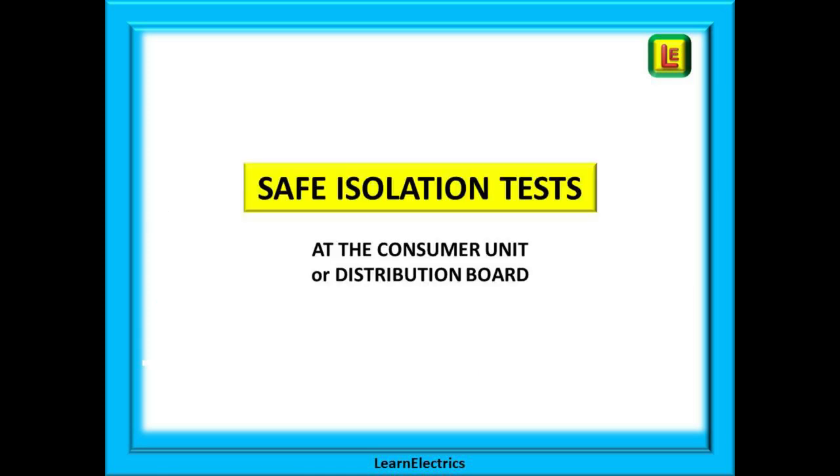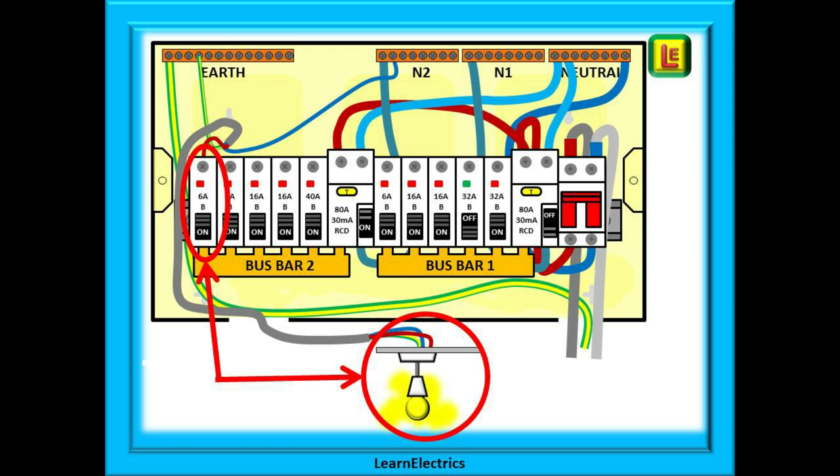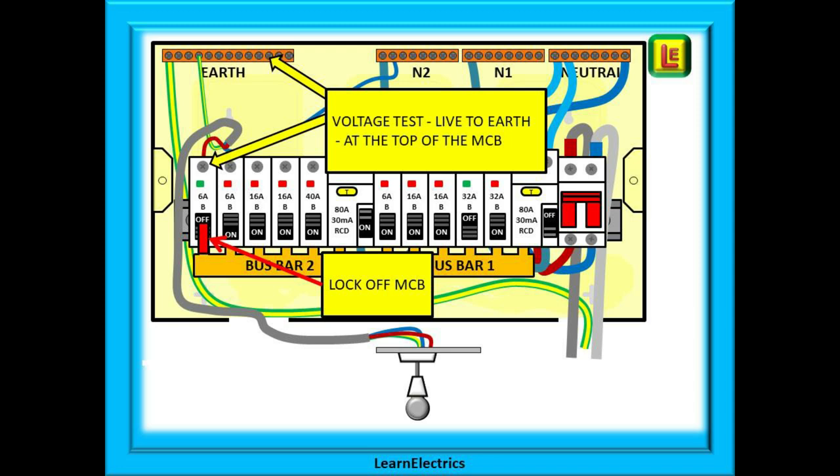We can look first at safe isolation at the consumer unit by isolating the circuit breaker for a circuit. Here we are about to safely isolate the 6 amp breaker on the left side of the consumer unit. With the MCB on and the light switch on, the lamp should be lit. Now turn the circuit breaker, the MCB off. The lamp should go off. If it does, we have chosen the correct circuit breaker. Now lock off the MCB. Attach a label so that others know who has locked it off and carry out a voltage test between the load side, the output side of the MCB and the earth bar.